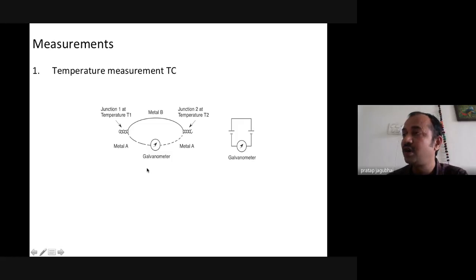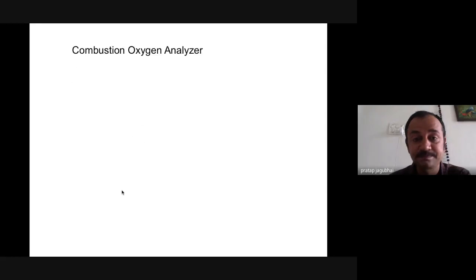The thermocouple generally used is the K-type, chromel-alumel, and it is widely used up to 600 degrees centigrade because it has a very good linear response between input and output. There are other types also, E, J, K, R, S, T. For higher temperature, you can go with the R, S, T types also, which are platinum-rhodium.